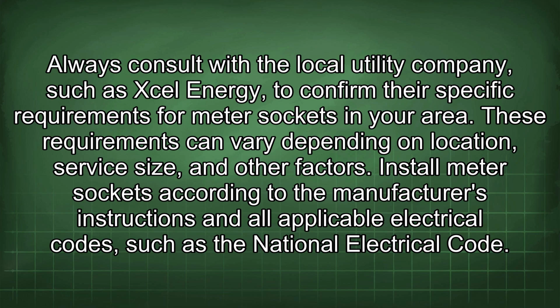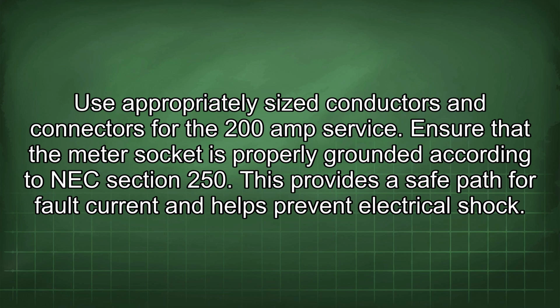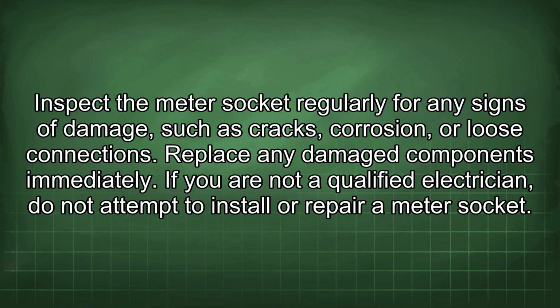Install meter sockets according to the manufacturer's instructions and all applicable electrical codes, such as the National Electrical Code. Use appropriately sized conductors and connectors for the 200 amp service. Ensure that the meter socket is properly grounded according to NEC Section 250. This provides a safe path for fault current and helps prevent electrical shock. Inspect the meter socket regularly for any signs of damage such as cracks, corrosion, or loose connections. Replace any damaged components immediately.